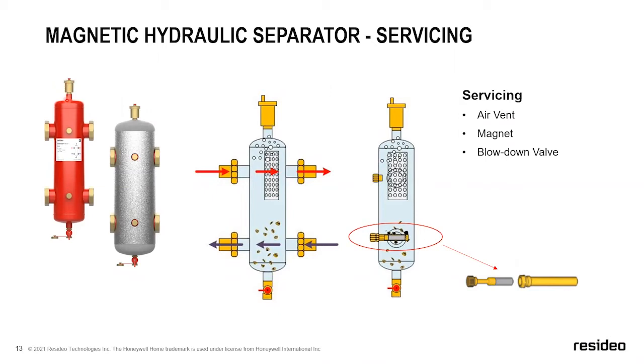When you start to unthread this, that check comes in, blocks the passageway of water, which allows you to remove the air vent and then take another one and screw it back in. On our bigger sizes, which I don't have an image of here, but on our flanged configurations that go from 2 inch to 6 inch, we've actually got a ball valve here.